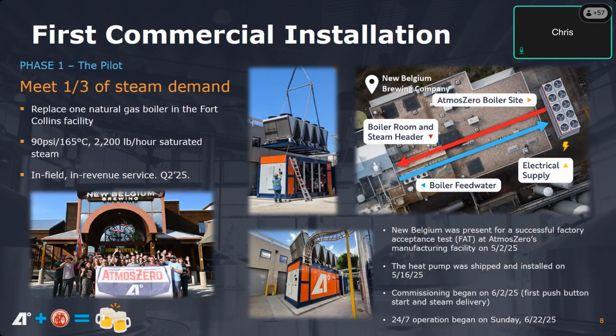One of the things we really wanted to do with this project was to prove to the market we can install a unit with zero downtime, which we successfully did. There were some double block and bleeds installed at the facility, which allowed us to tie in the piping and feed water lines in advance of the heat pump showing up. Once we shipped the heat pump, given we're only 45 minutes away from Fort Collins, it was shipped and installed in 1 day. Mechanical and electrical completion was about 4 days. The commissioning and commercial operation was about 2 weeks, and that's to get our boiler in line with their existing gas boilers, which they have a few different technologies there.